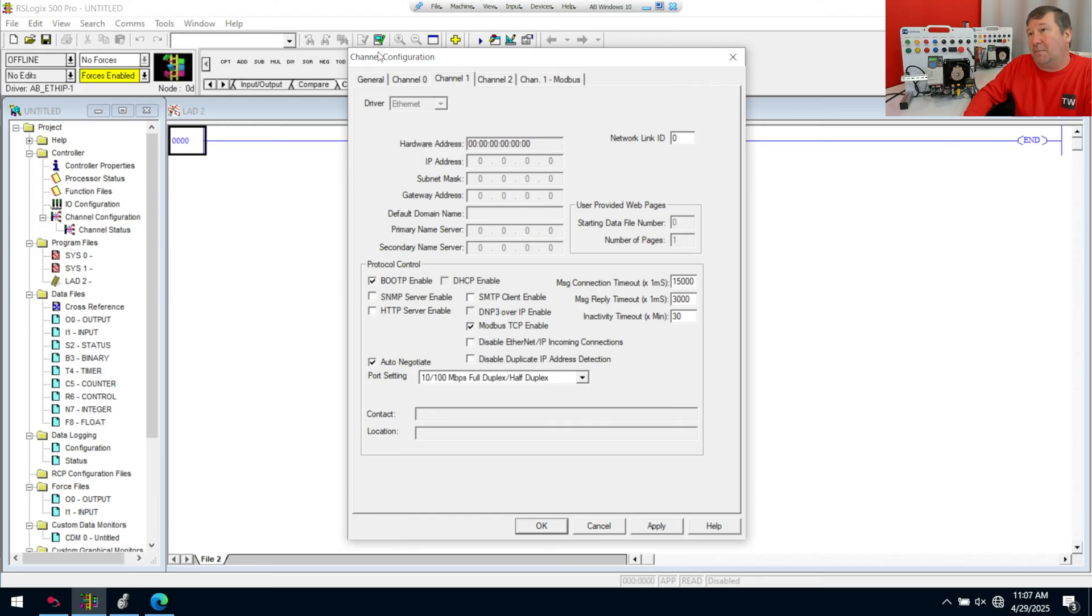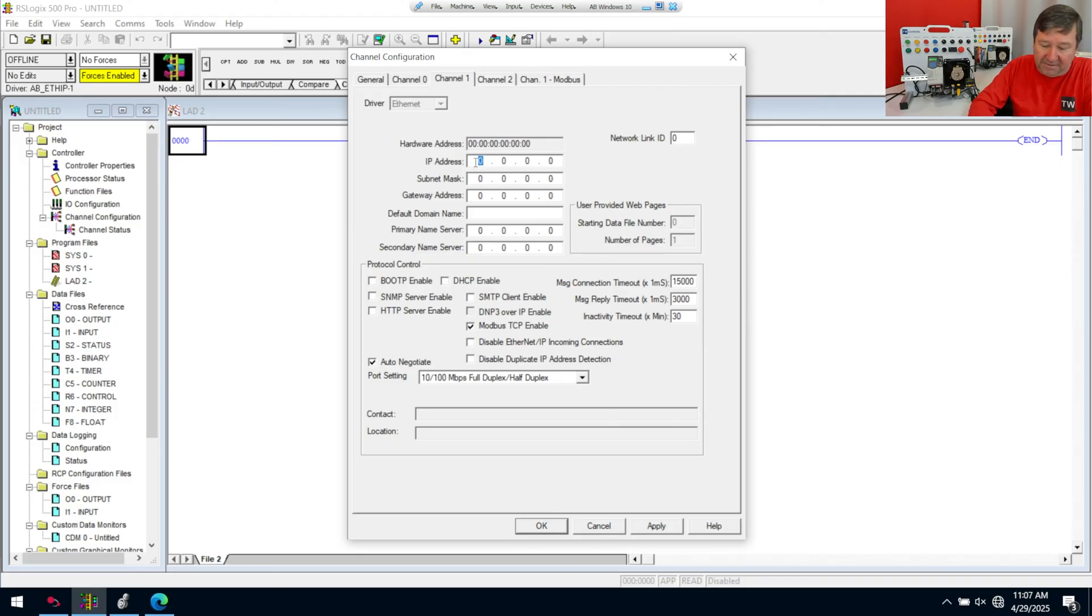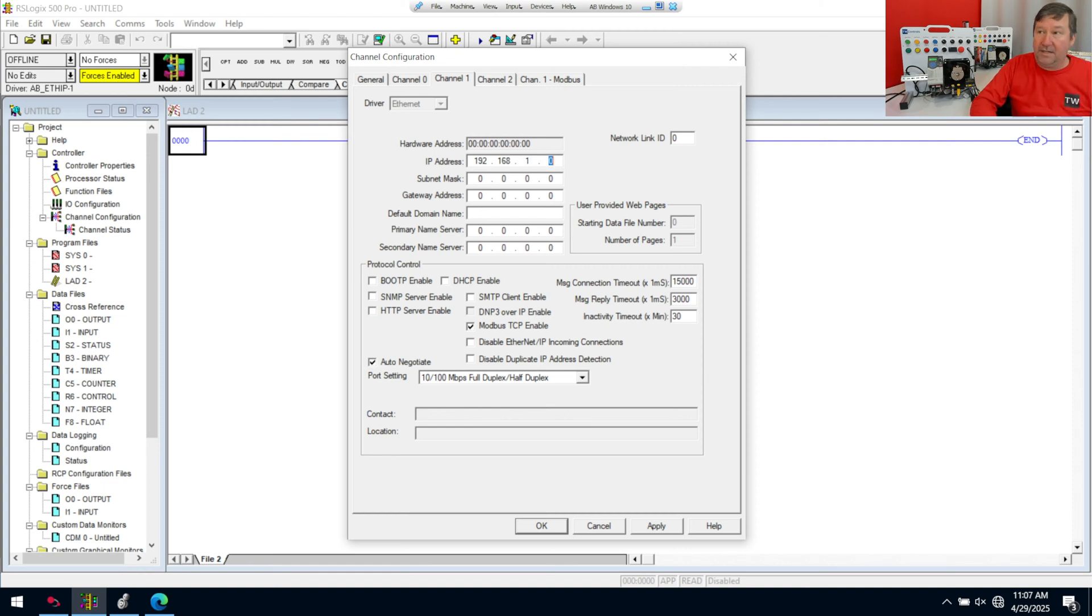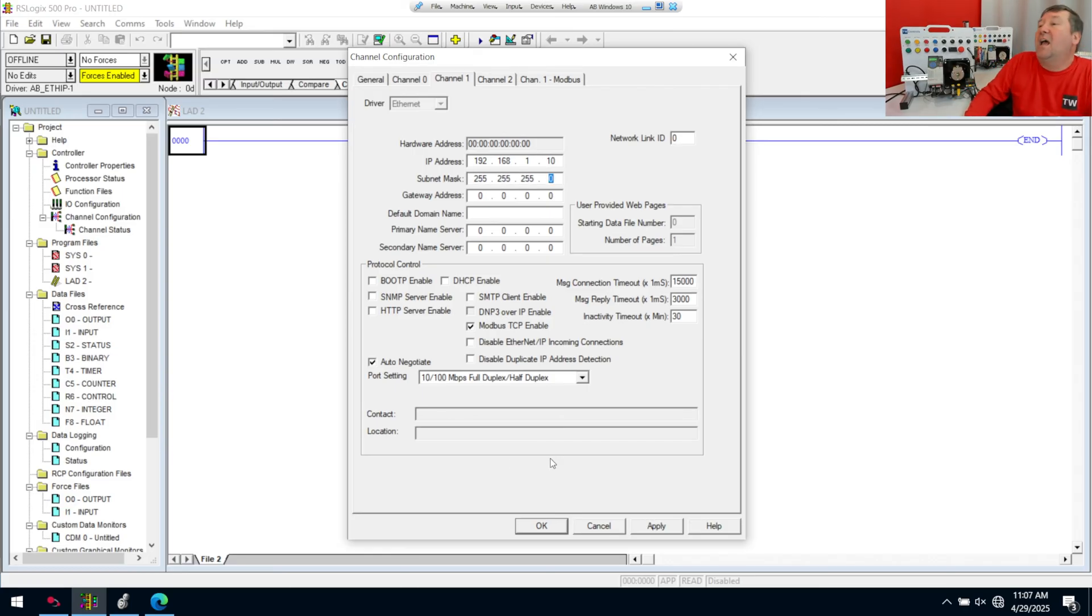And I'm going to go ahead and walk through it completely, even though we won't be able to actually test this out. We're going to uncheck the BOOTP enable and go in and enter the IP address at your PLC. If you're using one of our trainers, it's 192.168.1.10. And we have a subnet of 255.255.255.0.